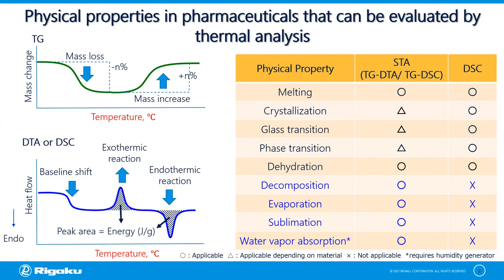Here is an illustration of a TG curve indicating mass loss and mass increase, and how the common reactions are represented in a DTA or DSC curve, both plotted against temperature. By combining both TG and DTA or DSC, we can elucidate reactions such as melting, crystallization, glass transition, phase transition, and dehydration, which can be measured by both STA and DSC. Other reactions such as decomposition, evaporation, sublimation, or water vapor absorption are recommended to be analyzed by STA.